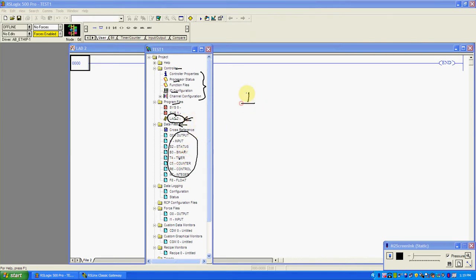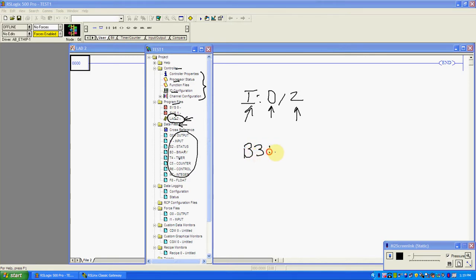For example, I colon 0 slash 2 — we're saying input data file, word 0, bit 2. Or if I said B3 colon 0 slash 4, that's binary data file, word 0, bit 4. This is just a way of referencing these data files. The rest of this stuff like comments and so on, we'll come back to in time.